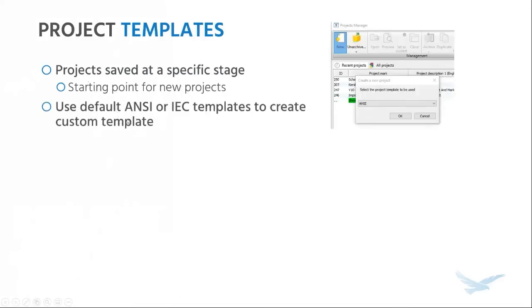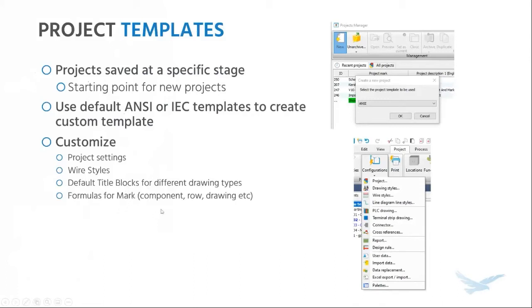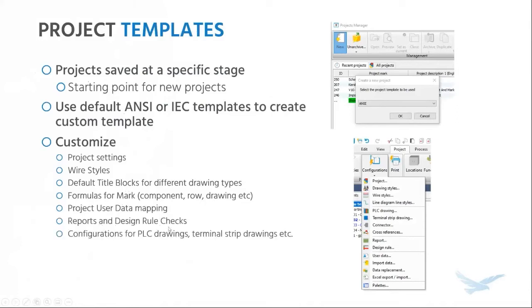The software comes with default ANSI and IEC templates, and I would recommend using them to build your custom template — essentially create a new project with the ANSI template, make your changes, and save it back as a template. Things you can customize in your template are: project settings, wire styles, the default title blocks linked to each drawing type, any kind of formula you would like to build for numbering your components, rows, drawings, etc., how you want to map user data for project properties, any reports and design rule checks you might want to add, and some default configurations for PLC drawings and terminal strip drawings.